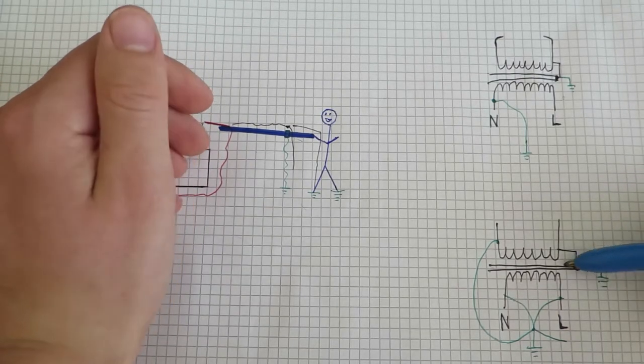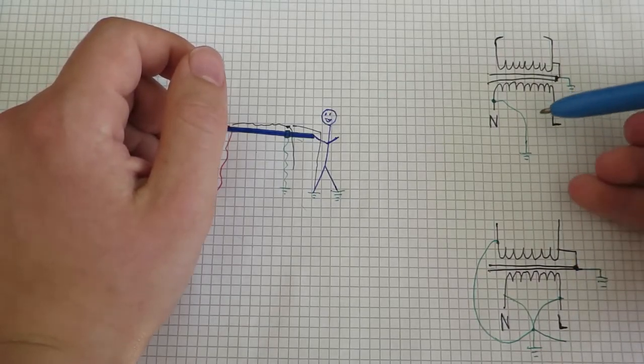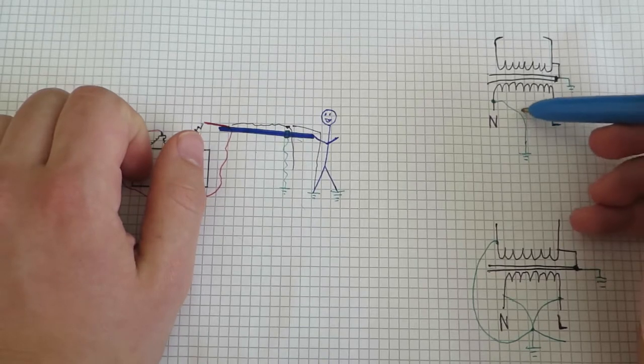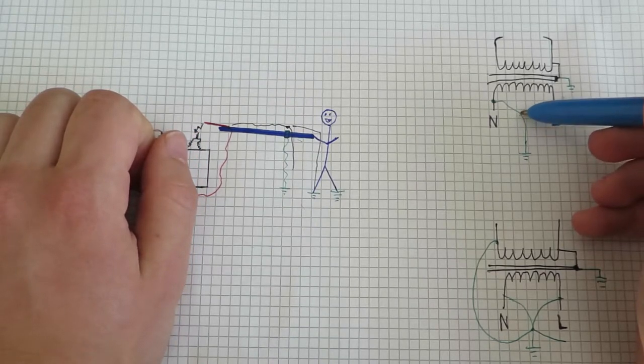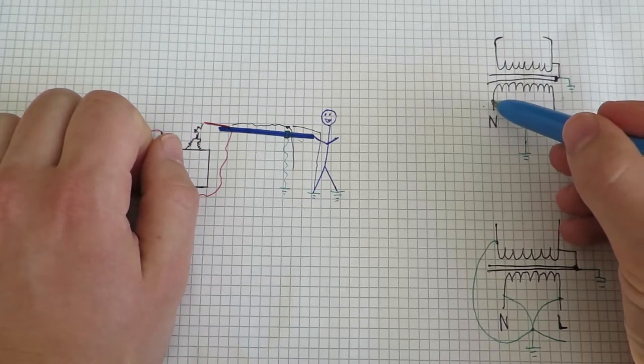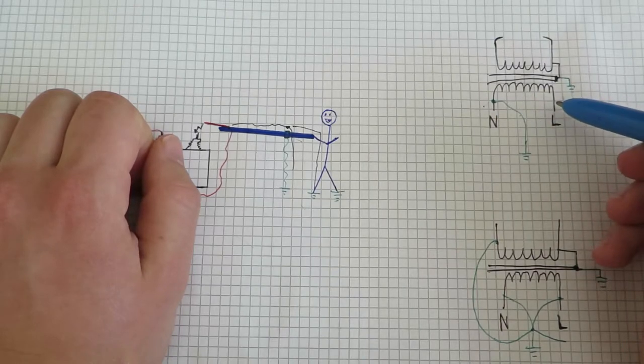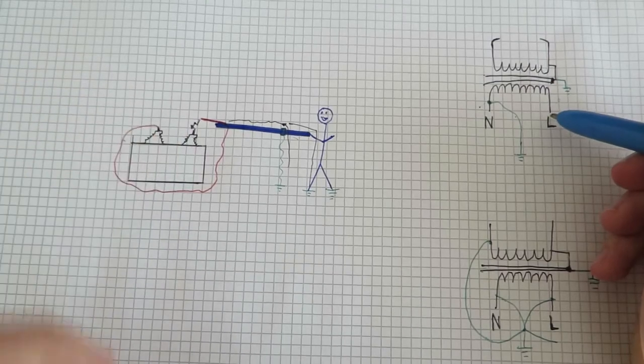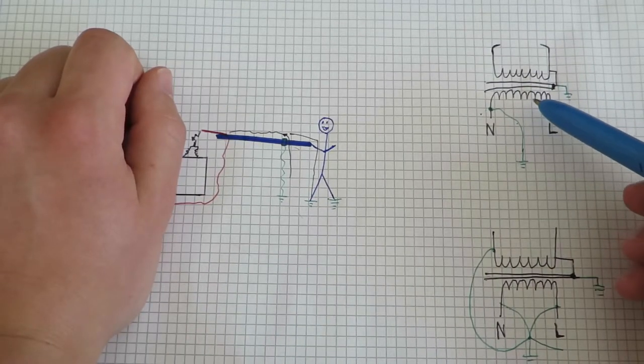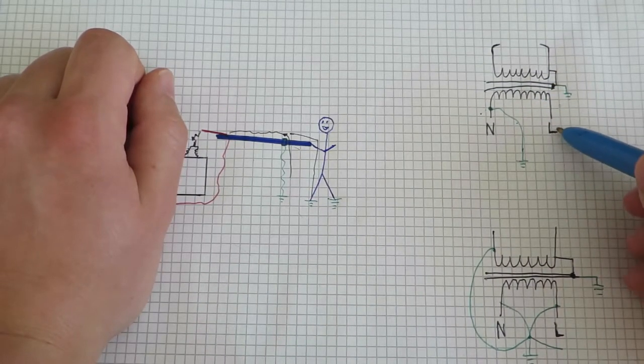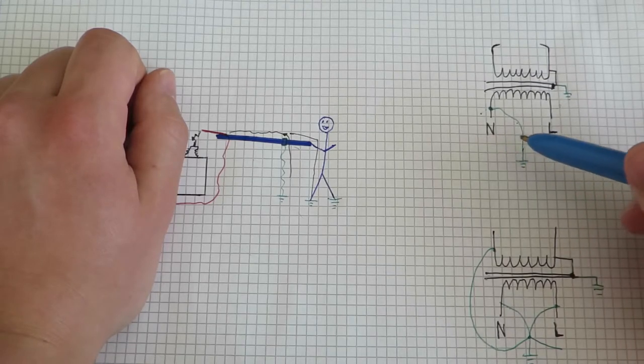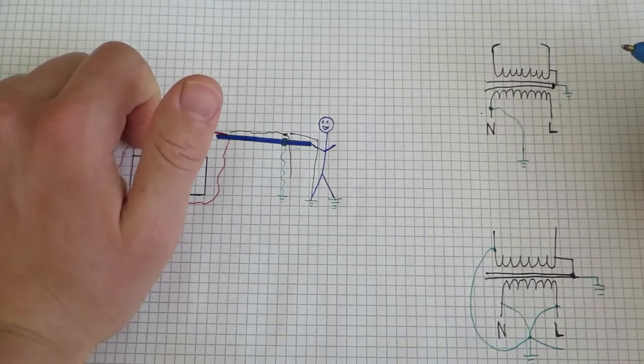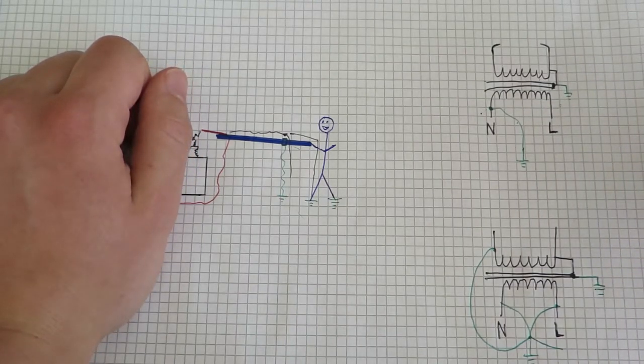Now, you got to be careful when doing this because you might think, okay, let's just connect just one alligator clip or grounding terminal to one of the pins of the transformers. But you definitely shouldn't do that because something like this could happen where you have your live here and your neutral here and you accidentally clipped your clip to the neutral conductor. Now, let's say the power would get turned on.